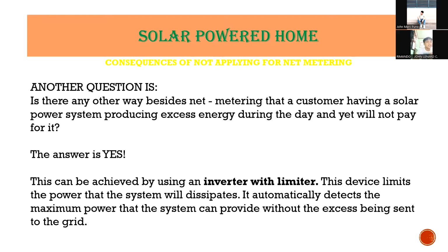Another question: is there any other way besides net metering that a customer having a solar power system producing excess energy during the day will not pay for it? The answer is yes. This can be achieved by using an inverter with limiter. This device limits the power that the system will dissipate. It automatically detects the maximum power that the system can provide without excess being sent to the grid.